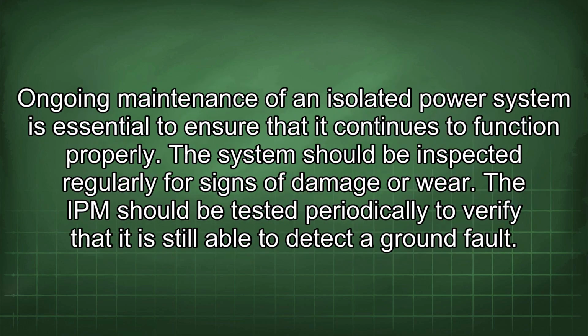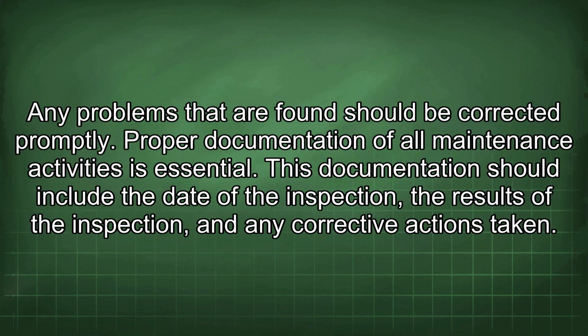Ongoing maintenance of an isolated power system is essential to ensure that it continues to function properly. The system should be inspected regularly for signs of damage or wear. The IPM should be tested periodically to verify that it is still able to detect a ground fault. Any problems that are found should be corrected promptly.